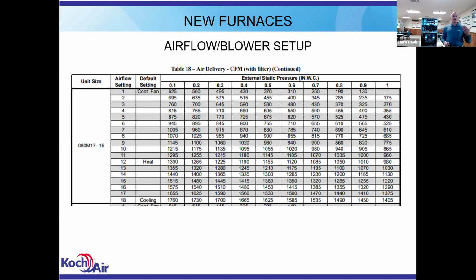On the heat setting, I'm going to set my heat fan speed according to my temperature rise. So when I'm doing a startup on a furnace, I fire it up, I let it run, I let it stabilize. I'll measure my temperature rise. Now I want to be about the midpoint to slightly below the midpoint of my temperature rise scale that's on my label. That way I know that's the birthday of that furnace. That's the best it's ever going to run its entire life. I've given myself some leeway either way for ducts getting clogged up, vents getting closed, things to change in the system. And my furnace can still stay online because I'm well within my temperature rise.